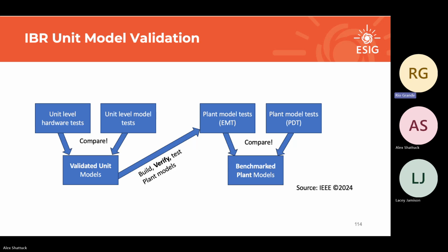So what I recommended in the design evaluation piece and in the IEEE and NERC world is that this falls onto the manufacturer, right? If you want to give me a good, detailed model and you want me to use it, give me a model validation report. That softens the blow a little bit for developers and transmission service operators, because when you start talking about a 1,000-page report of parameters where you have to check differences, no one has time for that. But this is something that's done at the manufacturer level already.